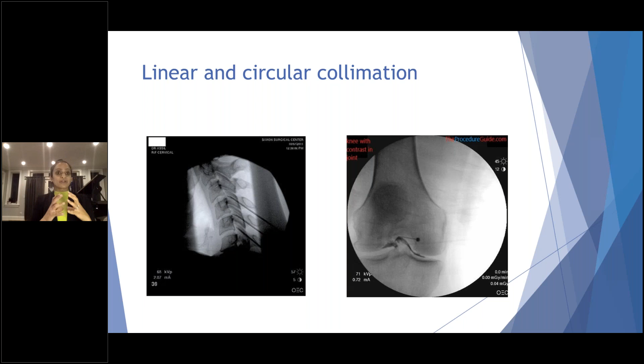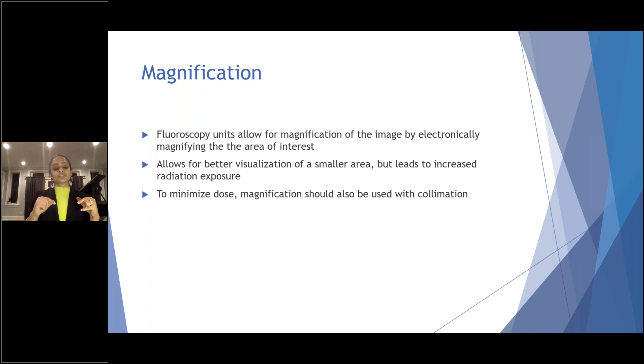All right, magnification. So fluoroscopy units allow us to magnify, and it's fabulous when you're like, oh, I don't know if I can really see that inner space for the cervical spine, and you can collimate and then magnify the image by electronically magnifying that area of interest. It does allow for better visualization of a small area, but it can lead to increased radiation exposure. So you really want to think about that and weigh that appropriately. So to minimize the dose when you mag, you should also collimate so that you're seeing that really direct area of interest with all the appropriate structures that you need, and then magnified.